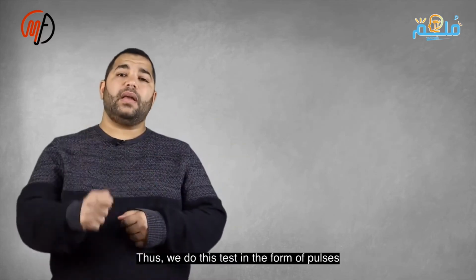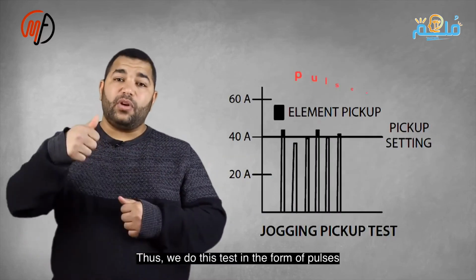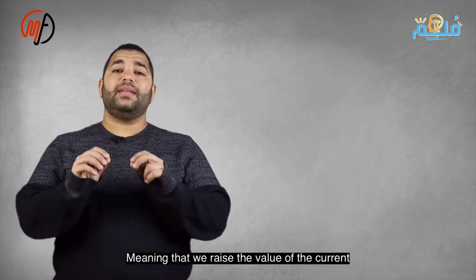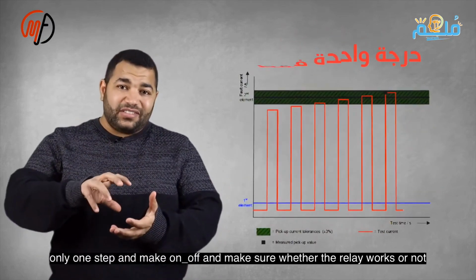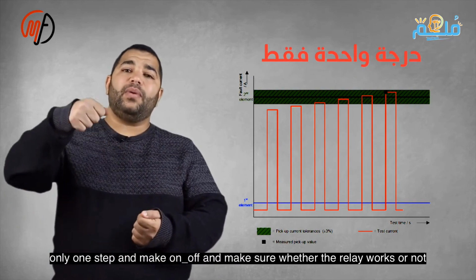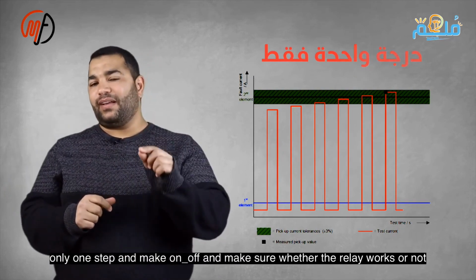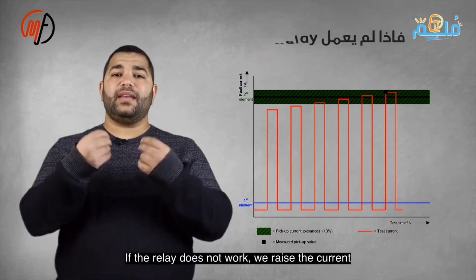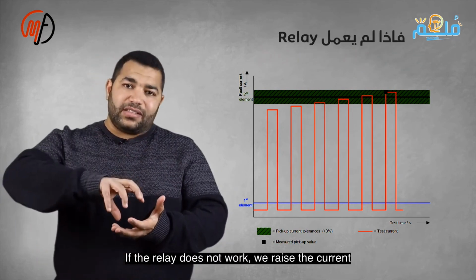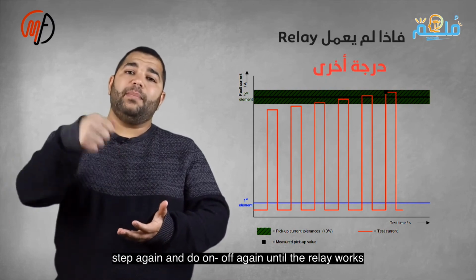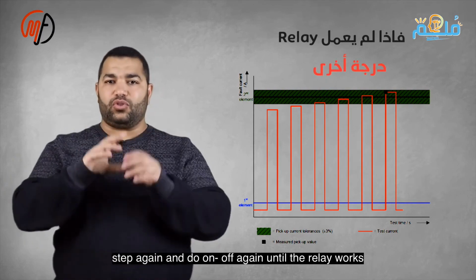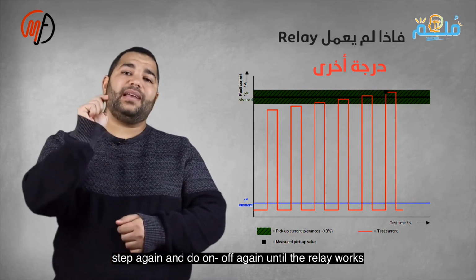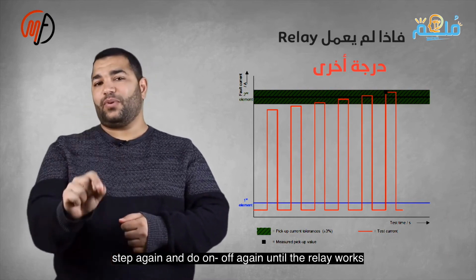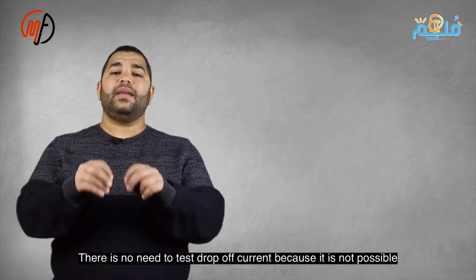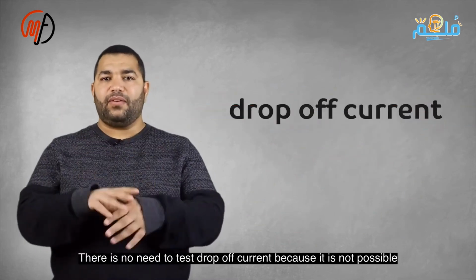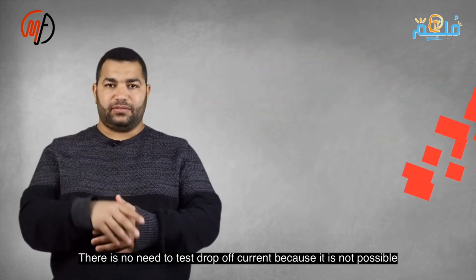Practical tips for testing overcurrent and earth fault are available. We increase the current step by step, performing an on-off test each time to check relay operation. If the relay doesn't operate, we repeat until it does. Avoid continuous injection for instantaneous overcurrent, and testing drop-off current is unnecessary. For earth fault, use the same method as overcurrent, but test only on the neutral, not the red, yellow, and blue phases. Key tips: confirm the wire's current rating before injecting to prevent damage. If the relay doesn't operate with a higher current than its pickup, verify it's a non-directional overcurrent relay.